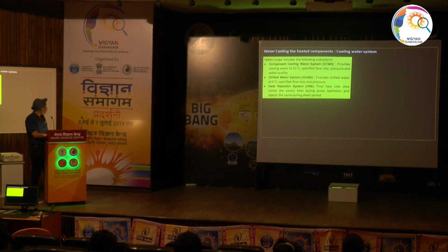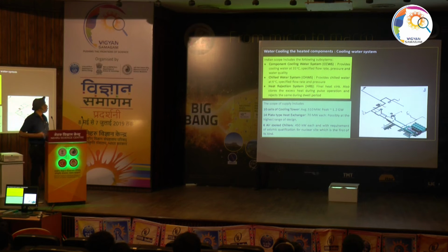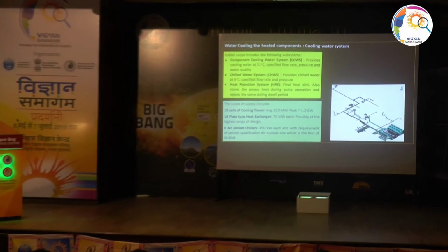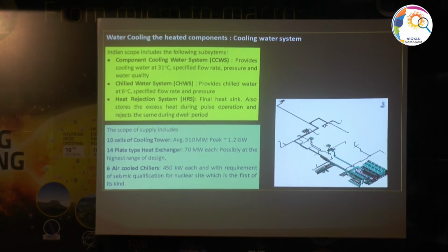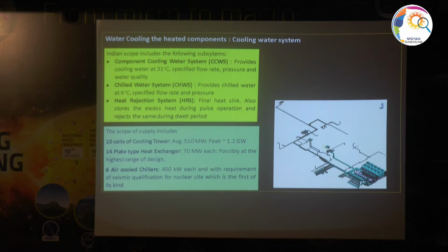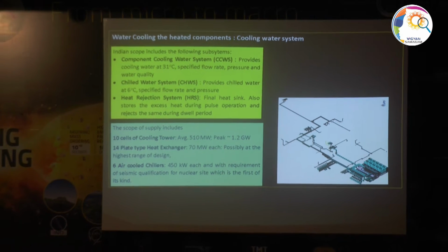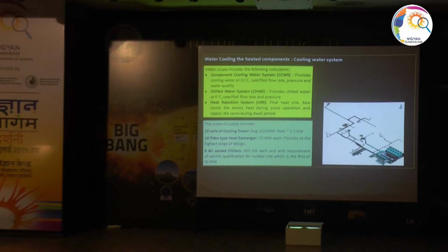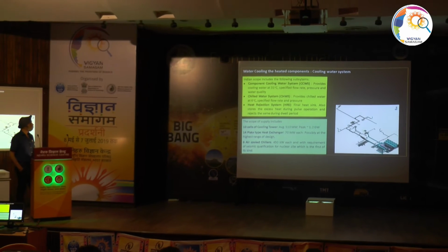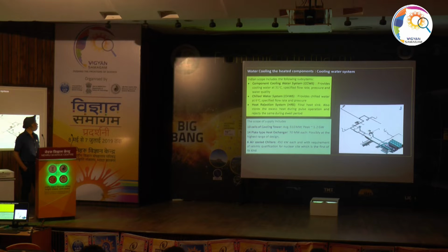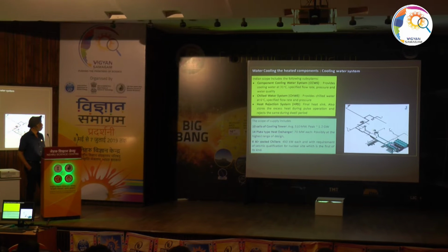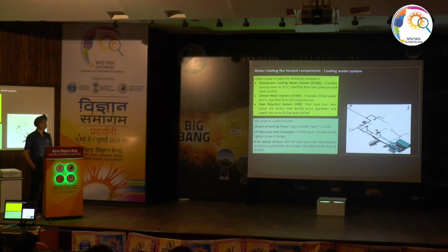What do these contributions consist of? They consist of 10 cells of cooling tower, and the cooling tower should have the capability of an average of 510 megawatts and a peak of 1.2 gigawatts. We have plate type heat exchangers, each having a capability of 70 megawatts, and possibly this is at the highest range of design. And 6 air cooled chillers, 450 kilowatts each, with the requirement of seismic qualification for a nuclear site. Now, this is another thing which is the first of its kind, but it's important from the ITER's operation point of view.